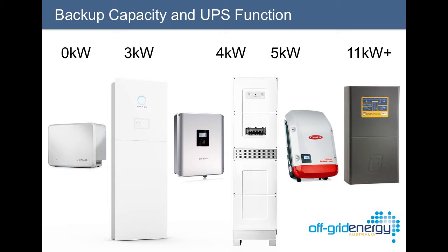Not all battery inverters or batteries can provide backup. Depending on how important this is for you, you might be in an area without blackouts, or where the longest one was an hour in the last three years, so it might not be a concern. But something like Enphase's AC battery doesn't have any blackout protection, so if the grid goes down, so does your battery and you have no power.